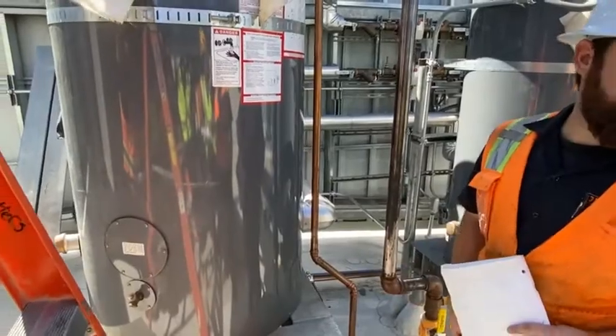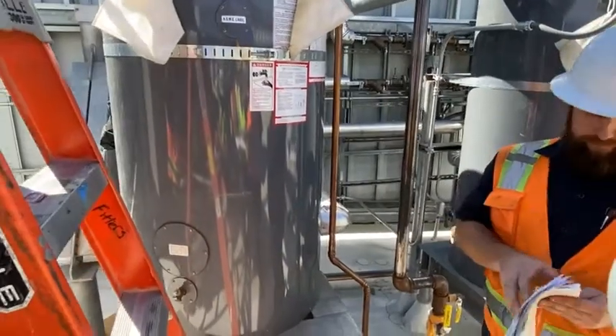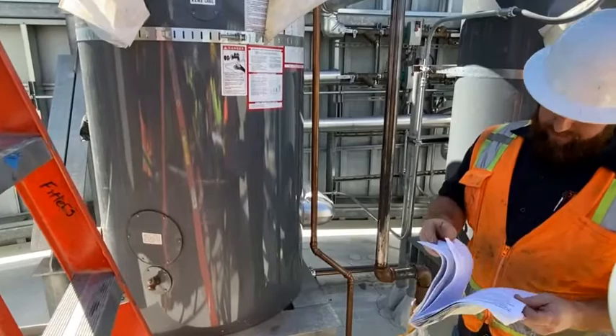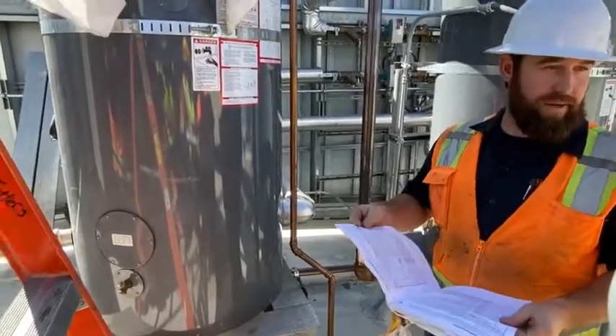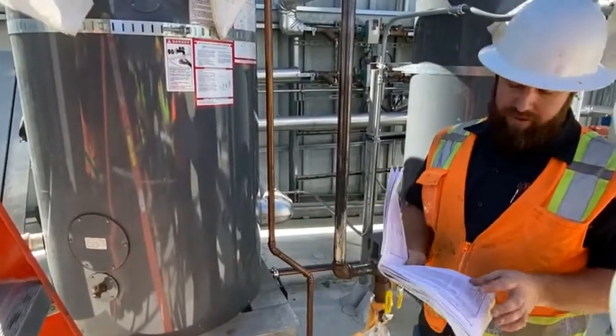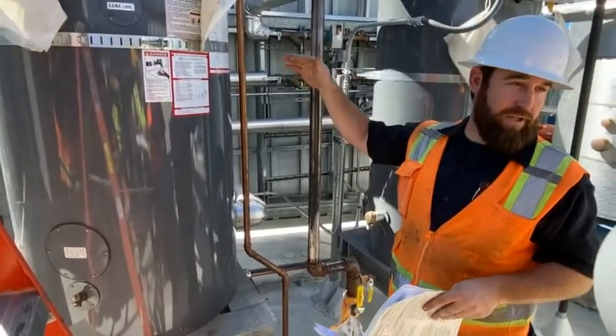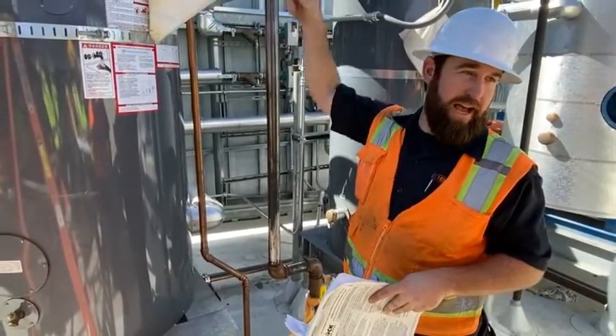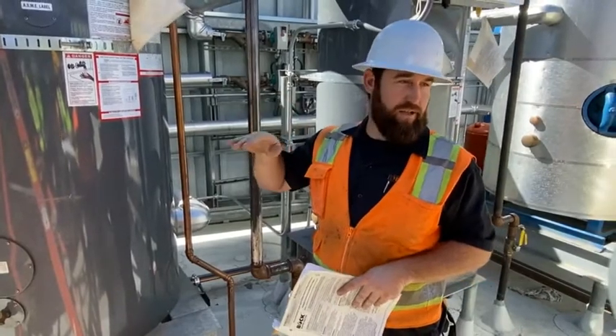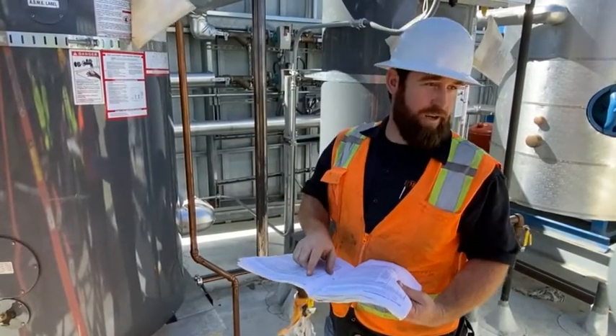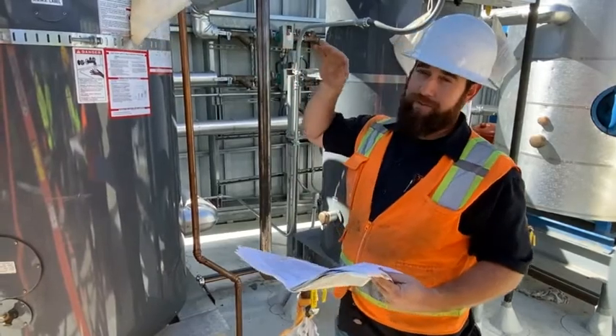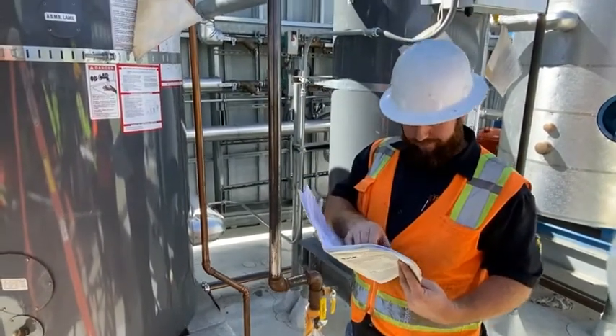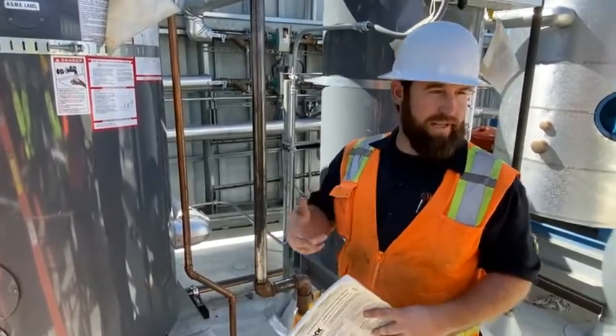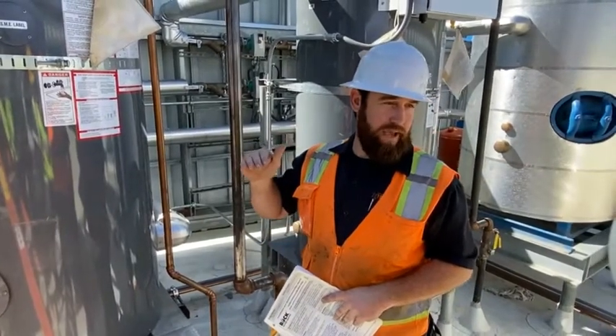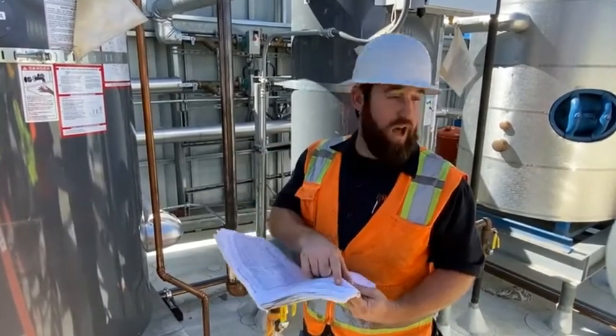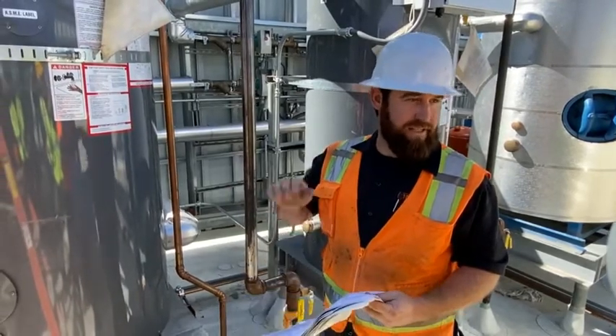What's the difference between the A's and the E's? One is just able to be reset, and the other one is not. So it's basically like low gas pressure. There's a gas switch inside, so if it notices that, it'll go into the blocking error code first. I think after 20 attempts, if it's still at low gas pressure, it'll go into the lockout error, where it has to be reset manually.